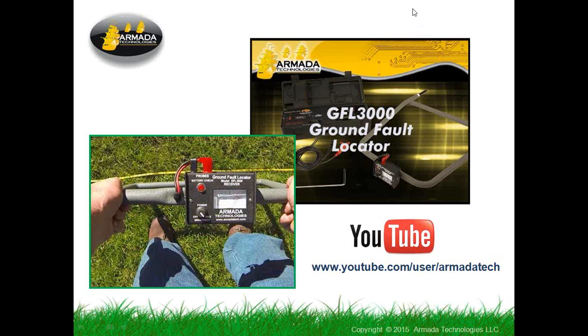So one of the things that he didn't do in the video there is to show you the crossways checking of the fault location. Once you go past the location and the needle's kicking in the other way, then you find the zero point where the needle is not kicking at all when it beeps. And then you turn it crossways at 90 degrees to the path of the cable and make sure that you have a null in that direction also. That's how you're going to get the real shovel width location of the fault, something to work with. So I should mention that.